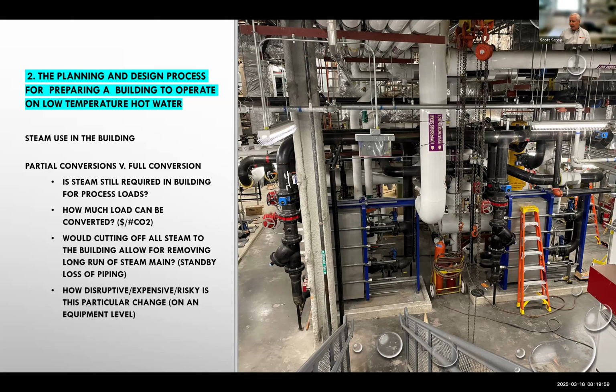Steam might be used for ventilation or makeup air preheat coils, reheat coils, humidification, domestic or lab hot water systems, process loads, perimeter heating with convectors, fan coils, unit heaters, cabinet heaters, valance units, radiant heating systems. And you have to decide if you're going to do a full or partial conversion.